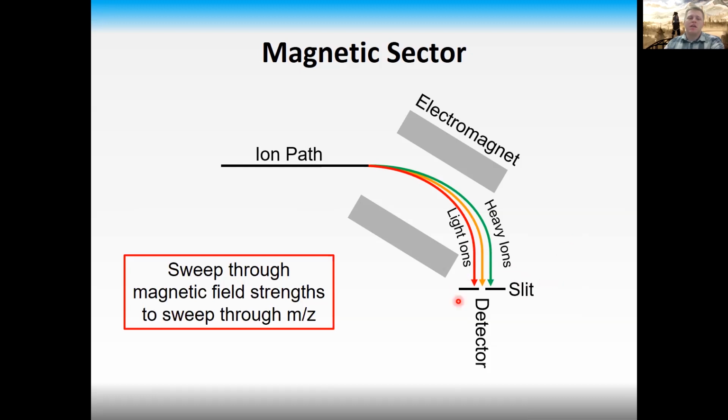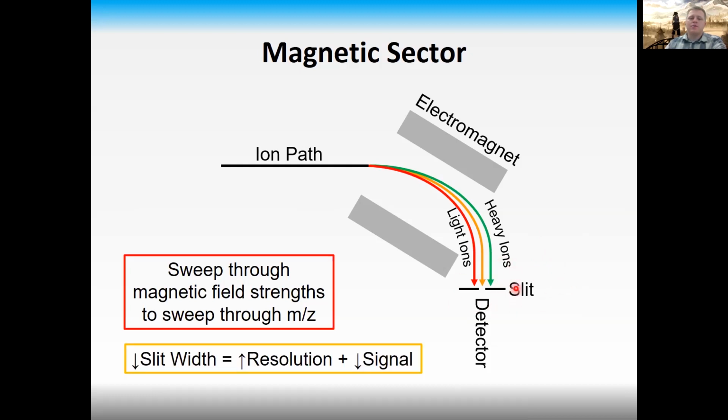And if you're really careful and have a high concentration in your analyte solution, you can get down to 3 decimal places sometimes. But the real limiting factor here is that as you lower your slit width to get better and better resolution, you're also decreasing your signal. Similar to in UV vis, when you change your slit widths, with higher slit widths, you'll get higher signal, but worse resolution. With lower slit widths, you'll get more resolution, but lower signal.